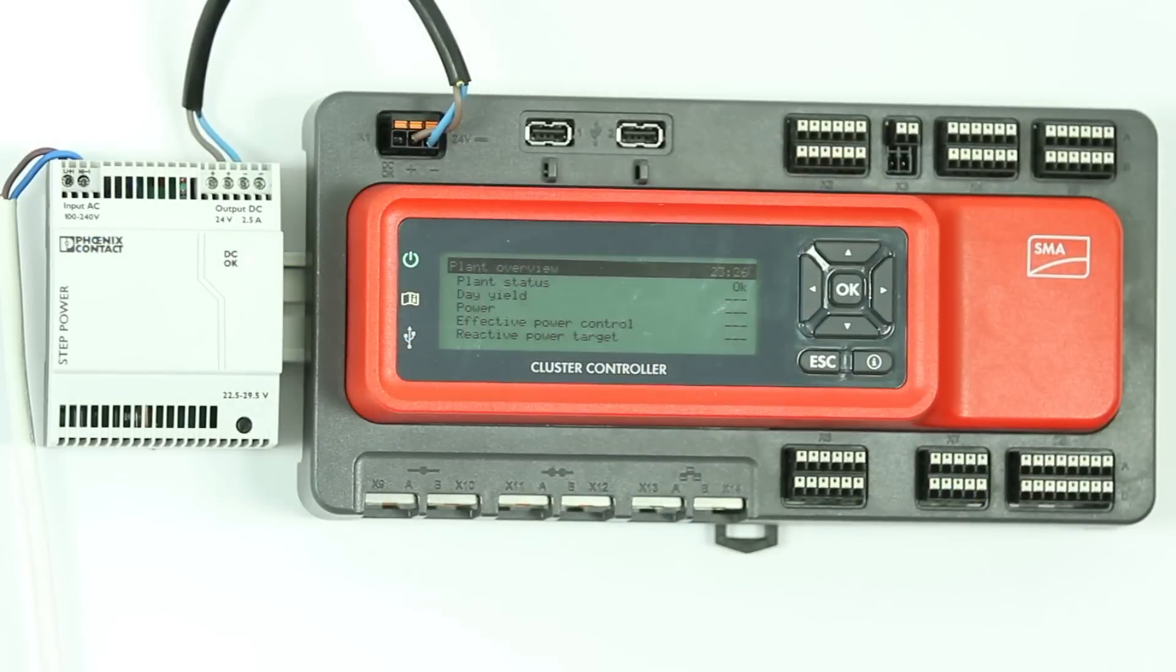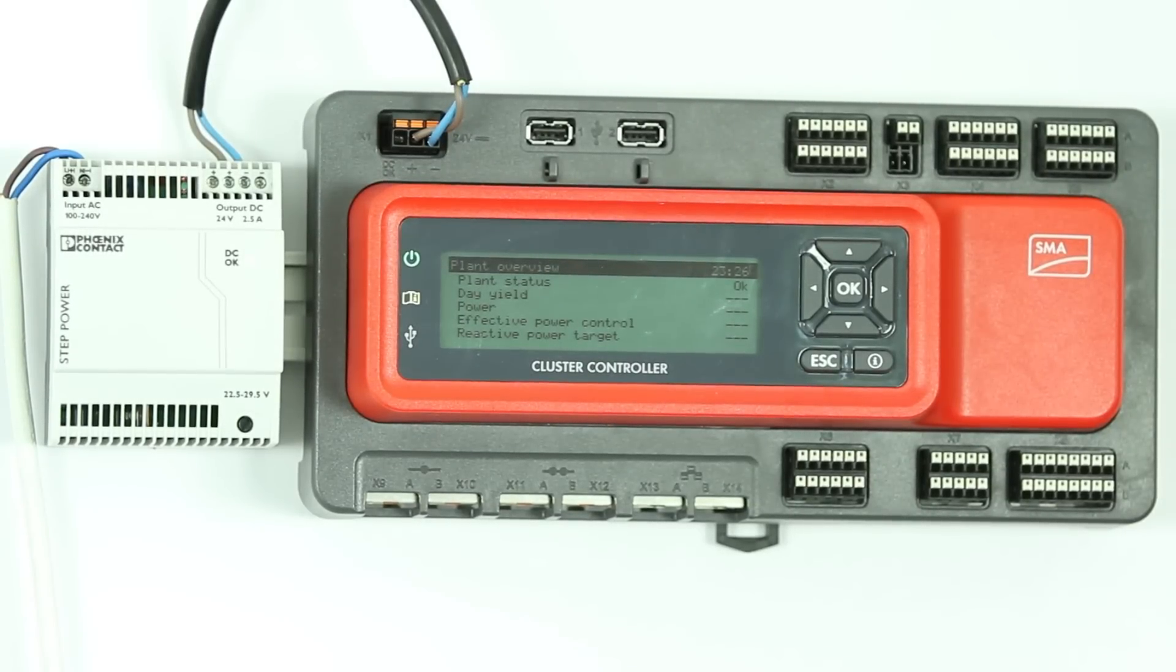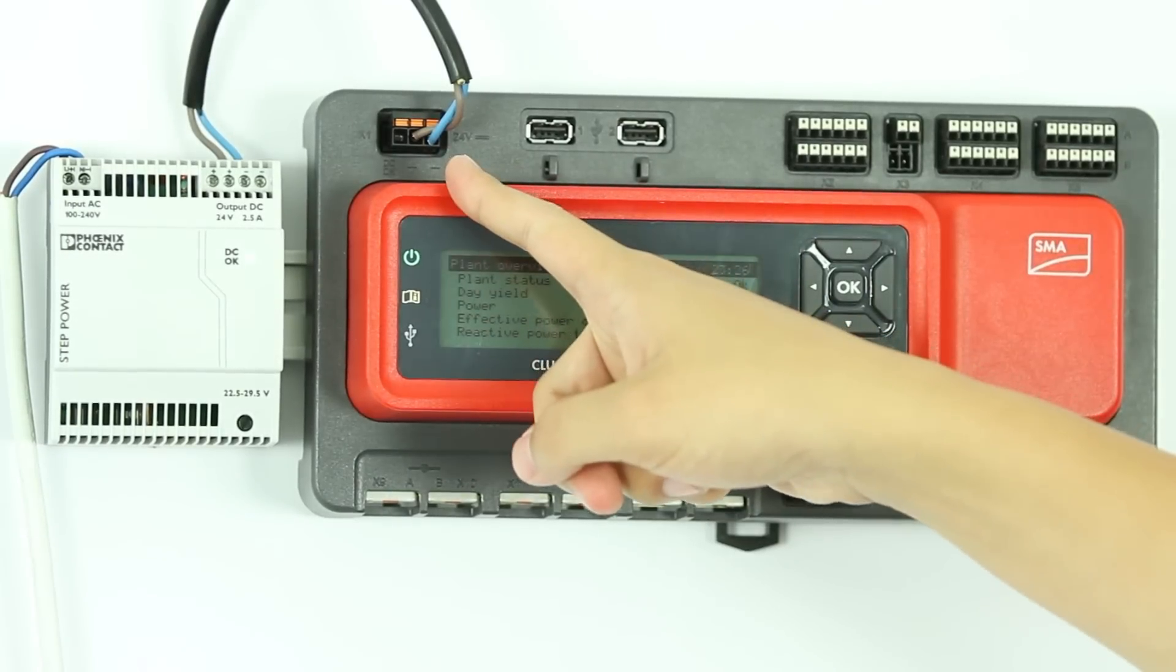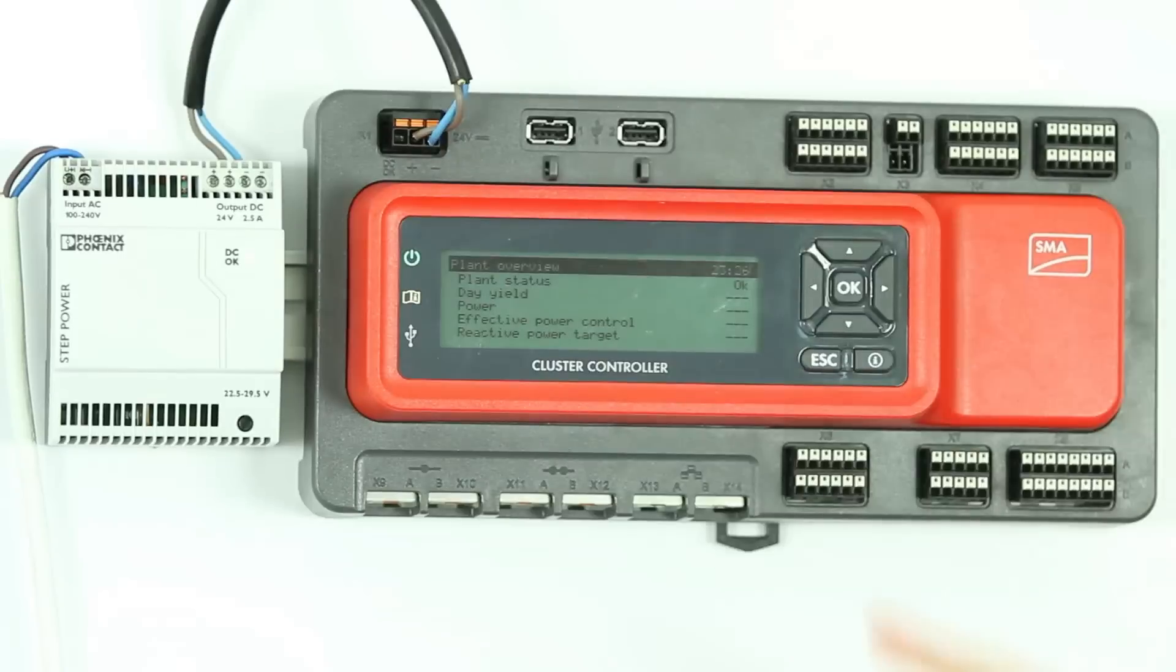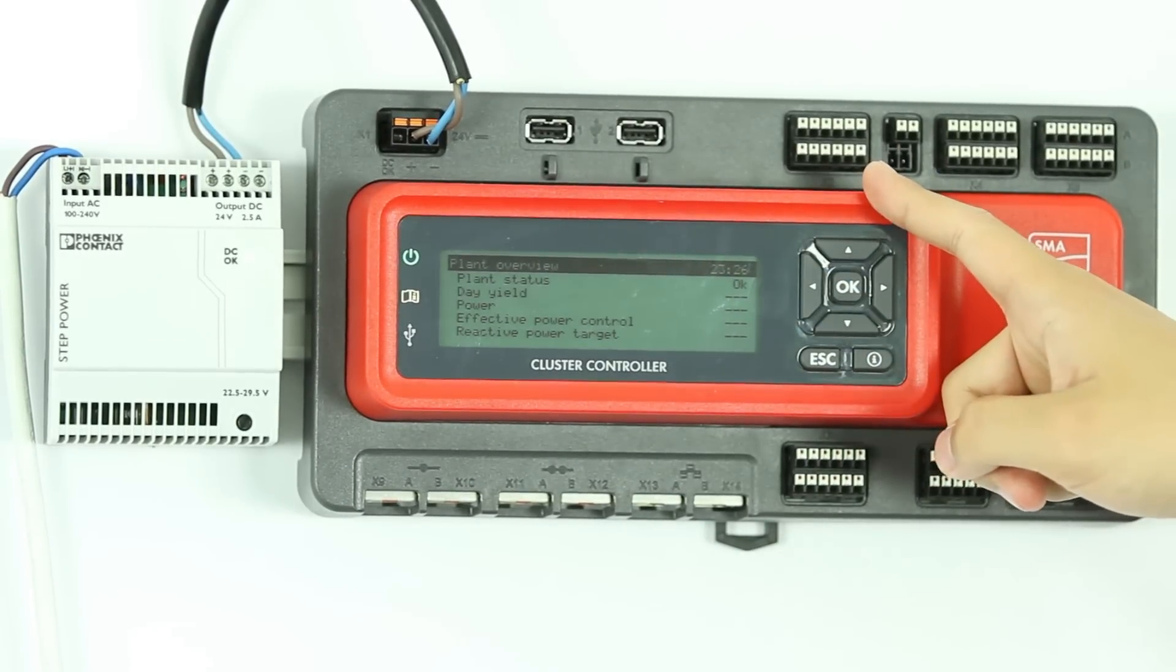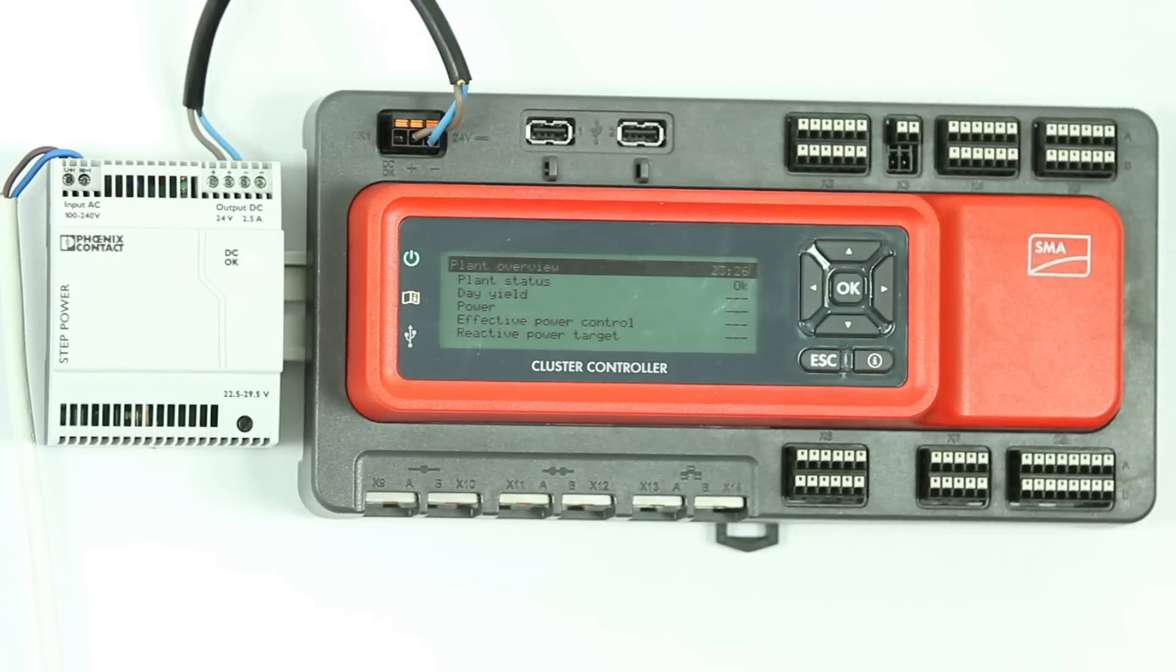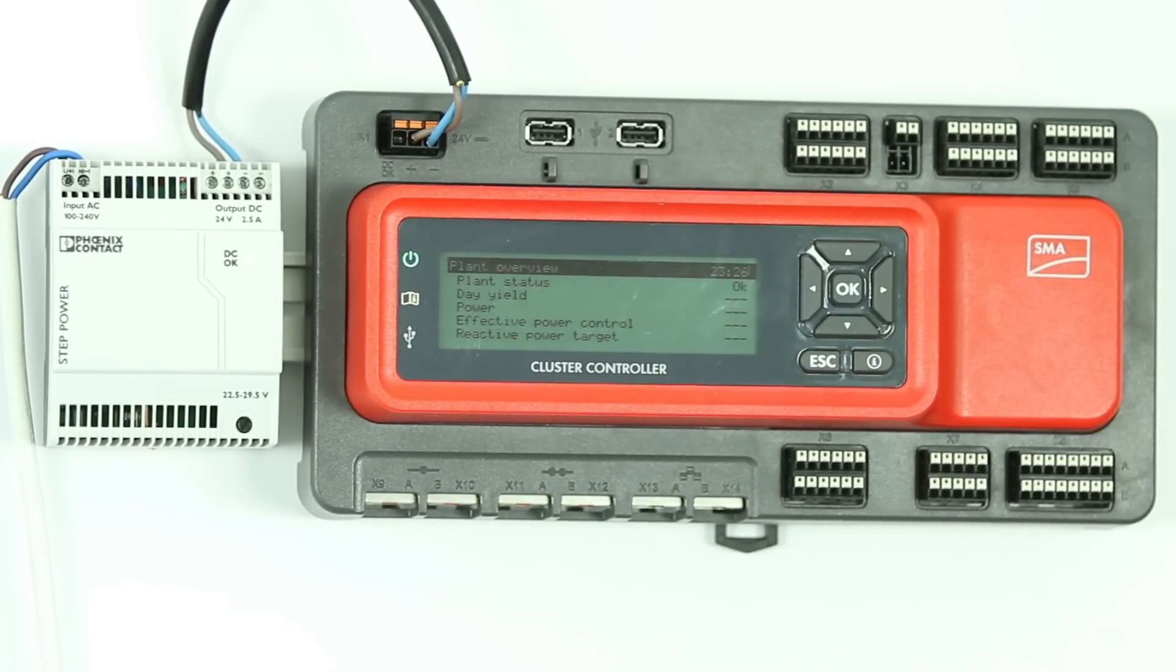As you can see here, the Cluster Controller comes with multiple ports for sensors and grid management specifications for active and reactive power setpoints. Here we have X1 for the 24-volt power supply, USB1 for data storage, USB2 for updates. X2 allows for three digital outputs for status indications on failures, warnings and active power limitations. X3 is reserved for future applications.